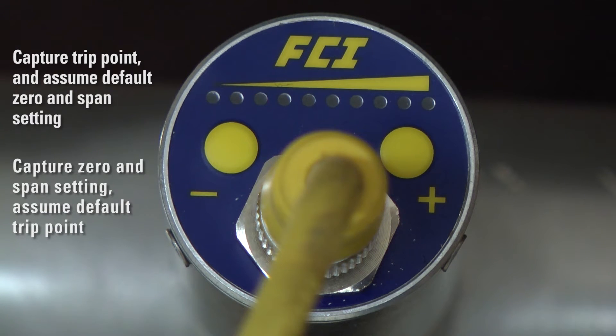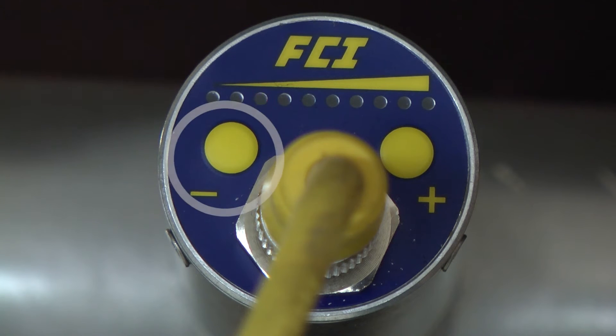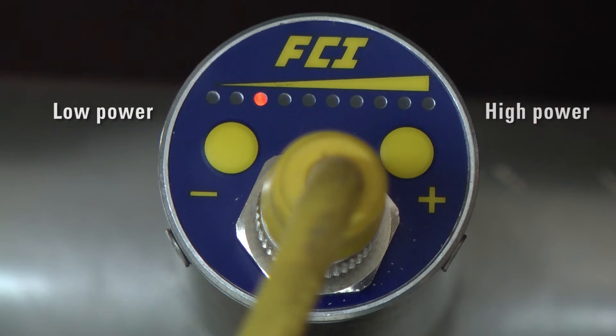In either case, entering with the minus or plus button selects the sensor excitation setting—low power or high power respectively—and exiting with the minus or plus button selects the fail safe, either low (minus button) or high (plus button).